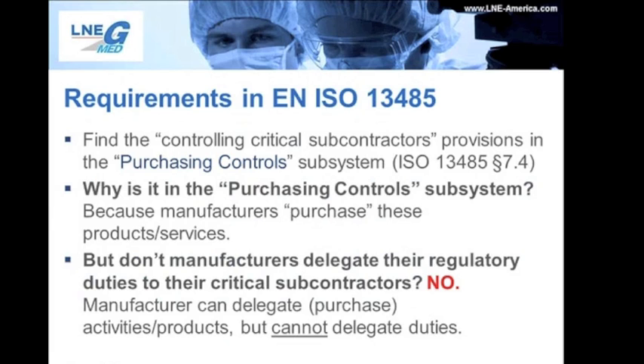In EN ISO 13485, the clauses that talk about how a manufacturer would control their subcontractors are in the Purchasing Control Subsystem, or Section 7.4 of EN ISO 13485. At first blush, this may seem like a strange place to put subcontractor controls, especially when a subcontractor or supplier is performing services. But think about it this way. Regardless if the manufacturer receives goods or services from their critical supplier or subcontractor, the manufacturer would still pay for these things, right?